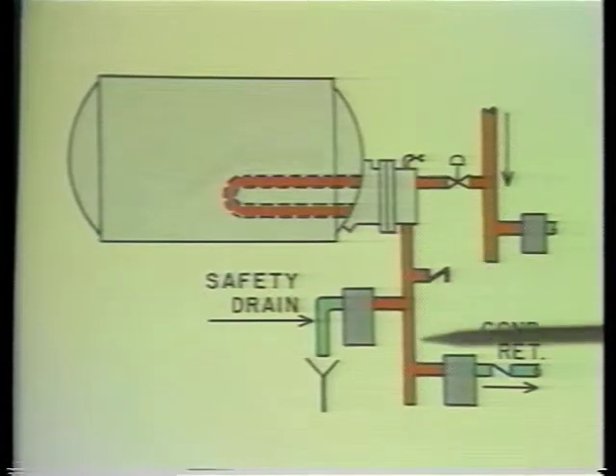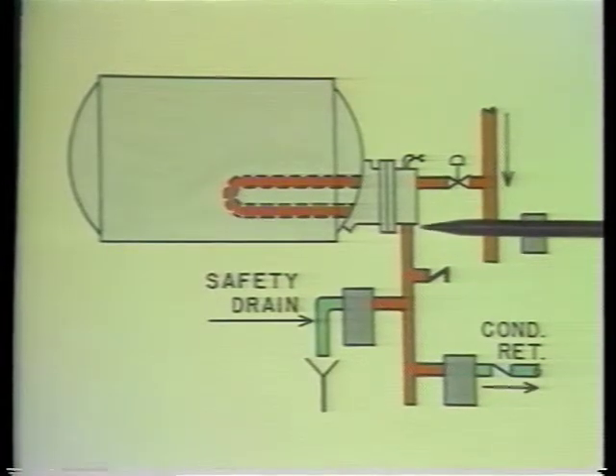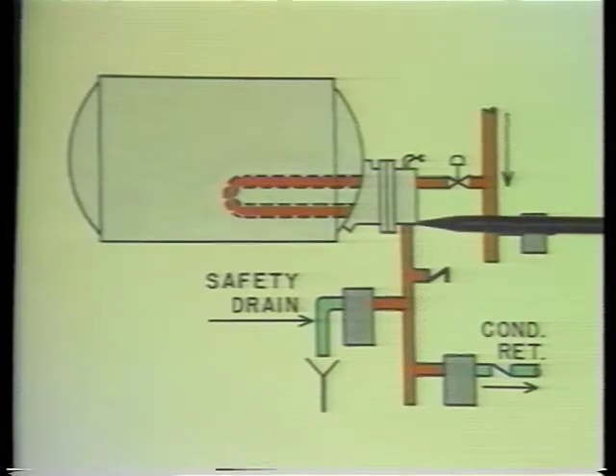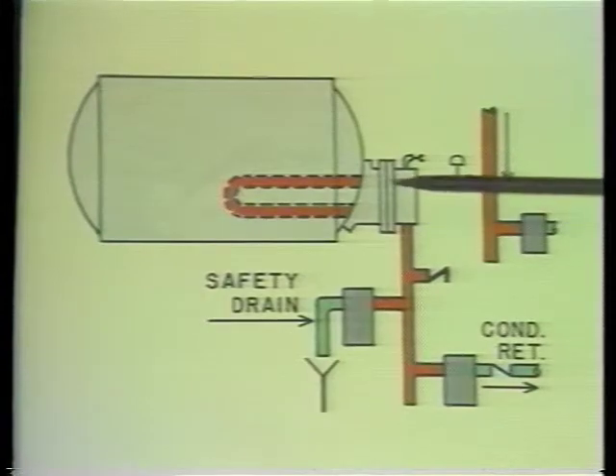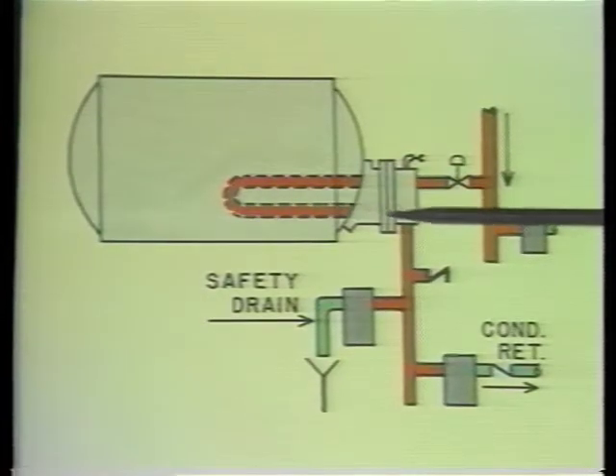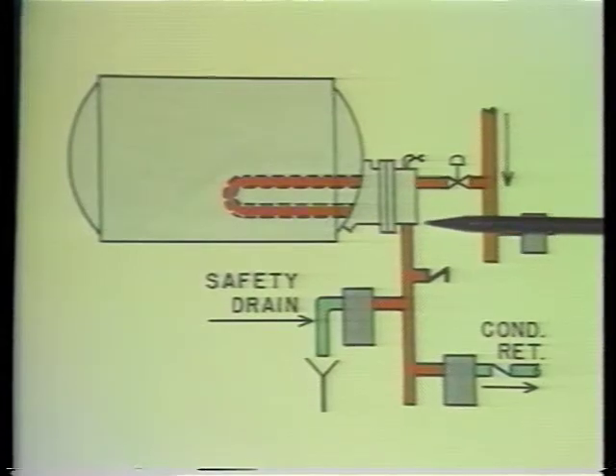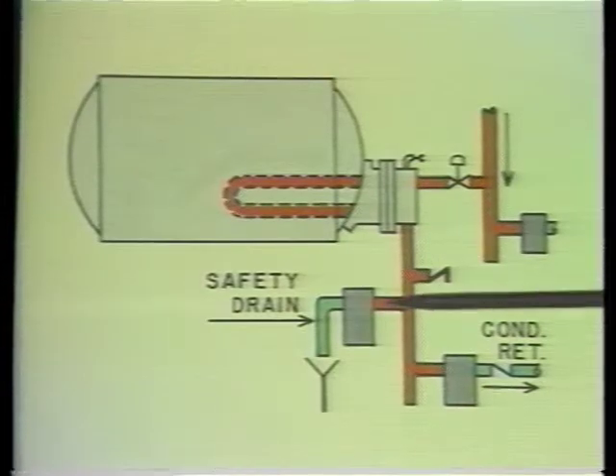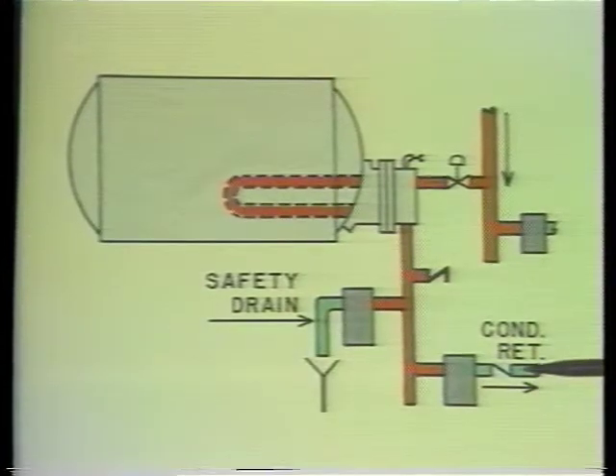A vacuum breaker and drip leg of sufficient height are essential to prevent the flooding of the heating tubes that can occur when the control valve modulates to extremely low pressure. It is essential that the horizontal heating tubes be kept drained of condensate at all times to avoid the damaging effects of water hammer and corrosion. Thus, a safety drain and check valve are highly recommended. The safety drain will discharge the condensate load when there is insufficient pressure available to overcome the back pressure in the condensate return line. The check valve will prevent the backflow of condensate into the tubes.